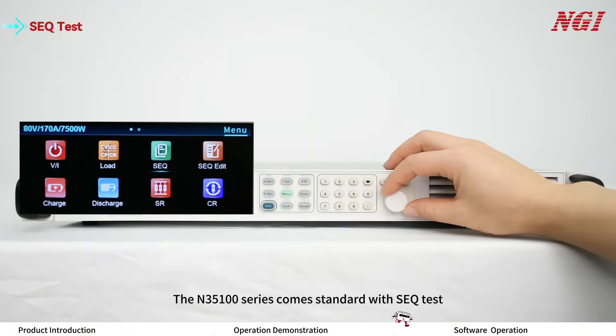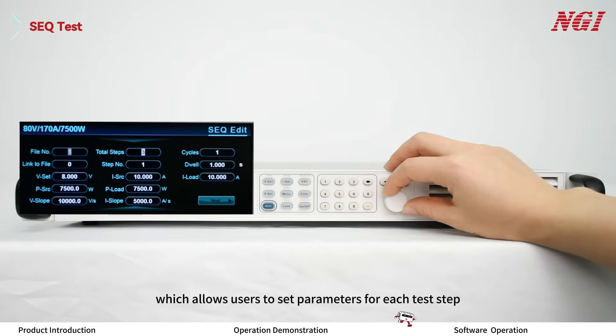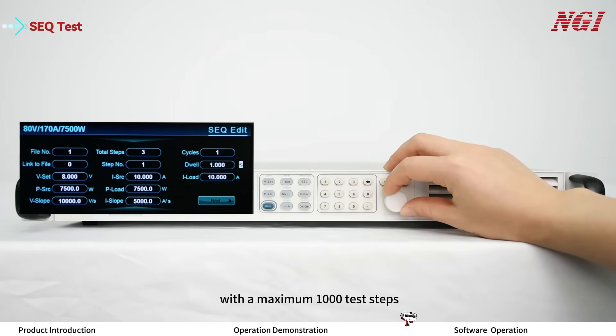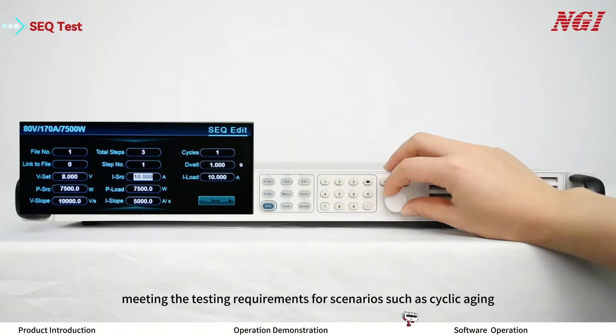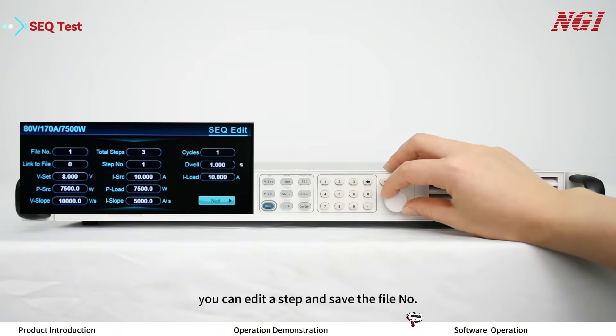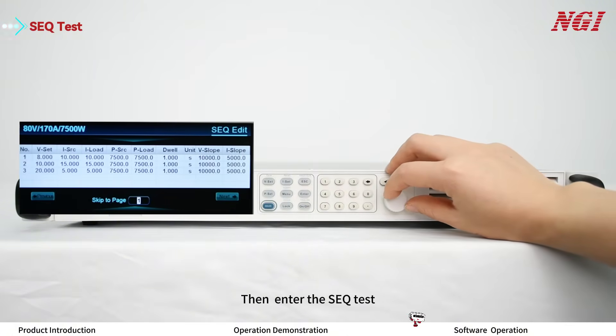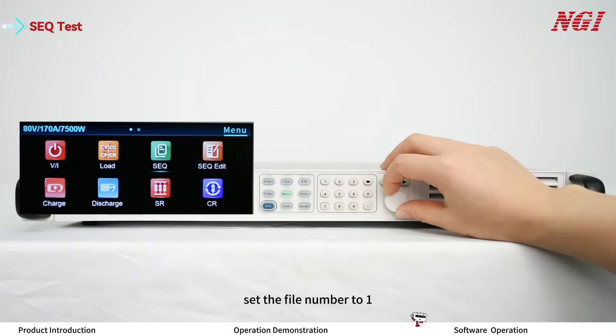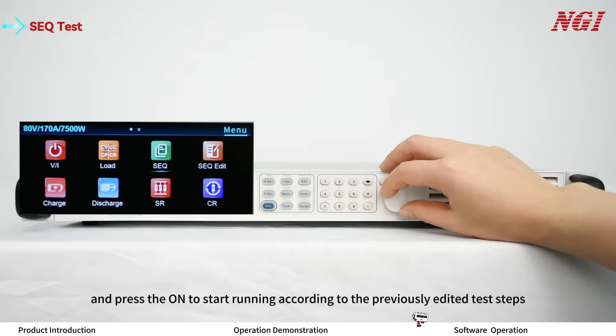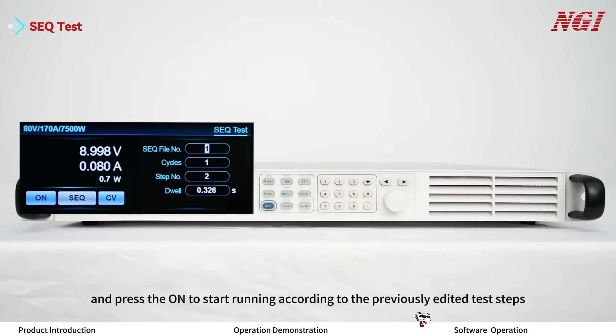The N35100 series comes standard with SEQ test, which allows users to set parameters for each test step with a maximum of 1000 test steps, meeting the testing requirements for scenarios such as cyclic aging. In SEQ edit, you can edit the steps and save to a file number — for example, file one — then enter the SEQ test, set the file number to one, and press ON to start running according to the previously edited test steps.